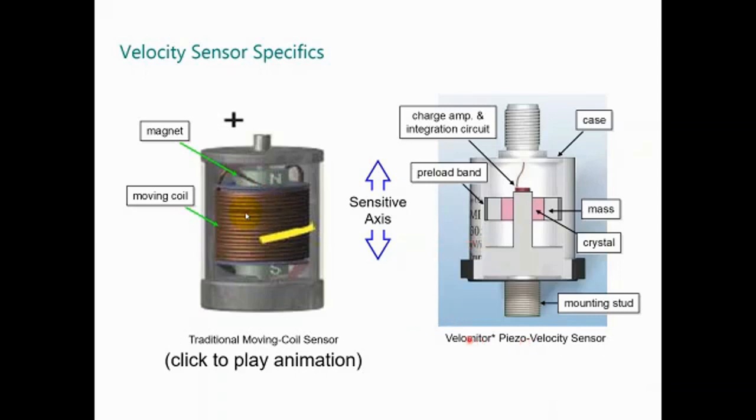The Velomitor is a trademark from Bently Nevada. It's also similar to a seismometer because it's a piezoelectric crystal in the preload band using the shear type design. Then it has a charge amplifier and integrating circuit, and this is isolated from the case.